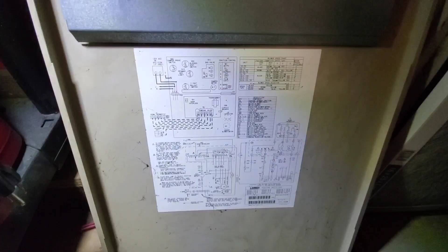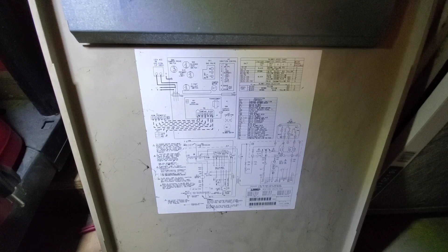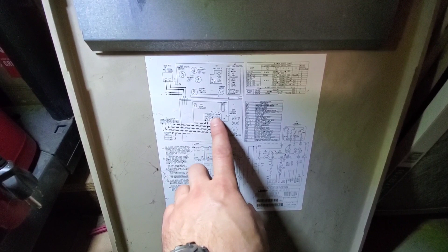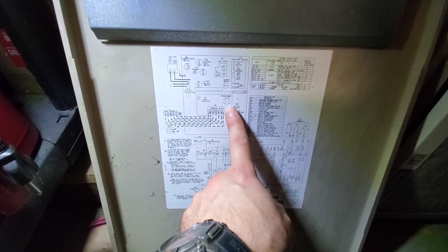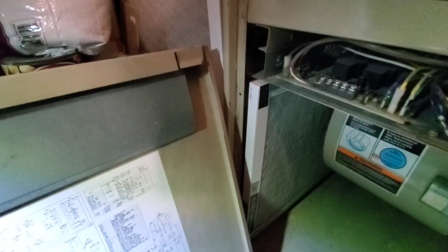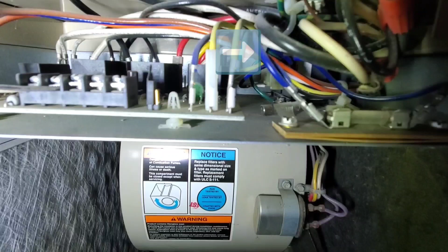So we have our board down here. This is our thermostat wire, so it goes into the terminals. So the black is R, the W is white. So for every electrical appliance, they have a wiring diagram. That's what this is here. So there's the step-down transformer for line voltage going into the step-down transformer. And that is this right here. It's in the back there that you probably are not going to be able to see. So behind the jumble of wires, behind the fuse at the bottom there, that is where the transformer is. So that will change 120 volts down into 24 volts.